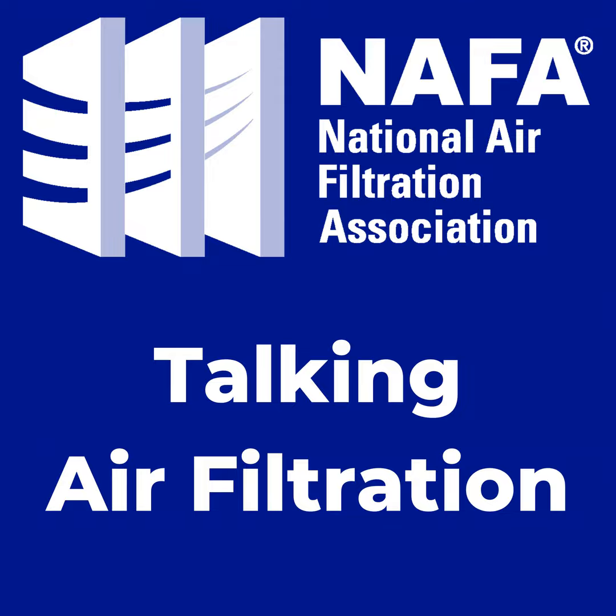So with the electrostatic charge, you have that MERV 15, but we know with Appendix J that a MERV 15 is not always going to perform as a MERV 15. The one filter I'm showing here actually dropped to a MERV 13 after the Appendix J test, because we're loading with the fine salt particles. You're not getting that true MERV 15 performance.